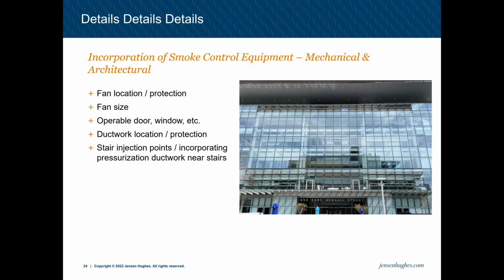Throughout the design phase, that's when you start to detail stuff more and more. You go from rough order of magnitude to specifics. And that could be specifics for fan location and protection and fan sizes, and then really for ductwork too. If you're starting to route stair pressurization ductwork or elevator pressurization ductwork through a building, figuring out how that necessary 2-hour fire resistance rating is provided, and whether they're going to use some kind of product like a fire wrap or fire rated ductwork, or if you might need to do some horizontal gypsum assembly, because all of those create their own specific concerns, which getting ahead of those concerns is very beneficial.